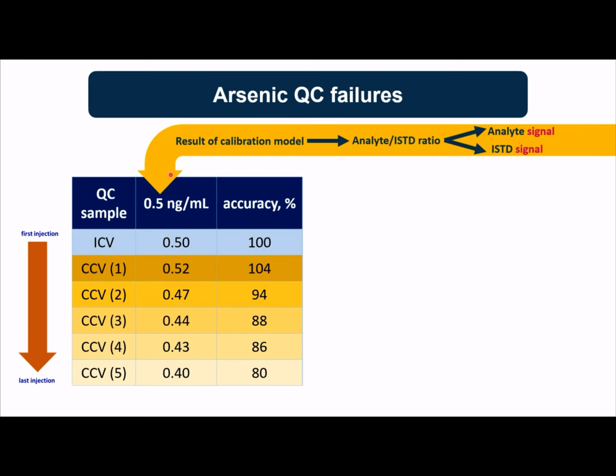These values are generated from a calibration model. That calibration model, in this particular case, was built on the signal and concentrations of the analyte as well as the internal standards. Those are then essentially built on the signal of the analyte and the signal of the internal standard. So I said, that's what I want to look at. I just want to go to the raw data, and I want to look at the actual signal.